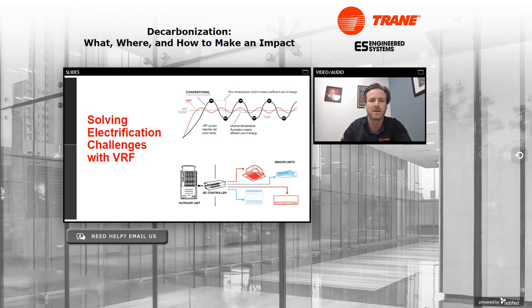Using the inverter compressor delivers exactly the amount of heat or cooling you need to the space, which prevents cycling, as you can see on the diagram at the top of the screen. A conventional system may bang the compressor on or off depending on set point, whereas VRF really seeks to hit the set point and keep it close, which keeps tenants more comfortable and uses less energy, a key component of electrification.